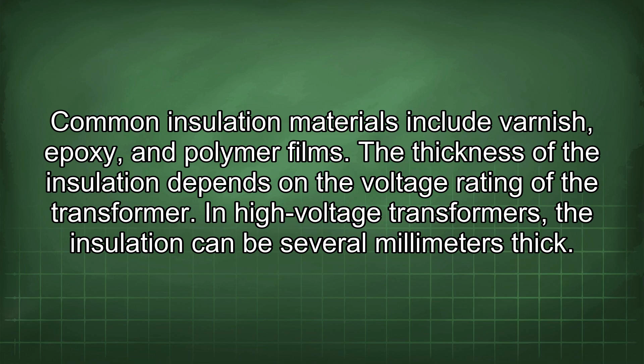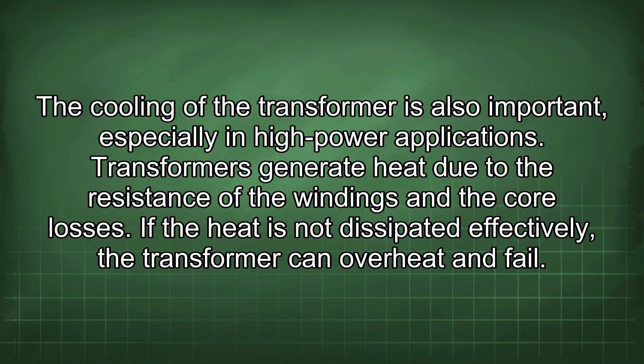The cooling of the transformer is also important, especially in high-power applications. Transformers generate heat due to the resistance of the windings and the core losses. If the heat is not dissipated effectively, the transformer can overheat and fail. Common cooling methods include air cooling, oil cooling, and forced air cooling. Air-cooled transformers rely on natural convection to dissipate heat. Oil-cooled transformers use oil as a coolant, which has a higher thermal capacity than air. Forced air-cooled transformers use fans to circulate air over the transformer windings.